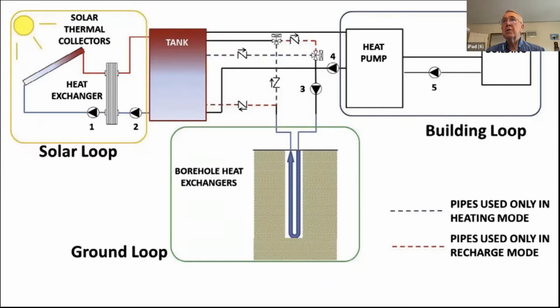So now you're warming up the dirt all around the borehole, or boreholes, plural. And this design is specifically for cold climates, actually. So they've got nice warm dirt in December and January to give warm water for the heat pump. Guess what? That makes it very efficient compared to air source or anything else. So if the sun doesn't shine for a week, no problem. They've got plenty of warm water from the ground loop. So the heat pump provides nice, efficient heating for the building. So this is a pretty good design, I think. Again, no air source mode, but solar thermal, ground source, and multi-source.